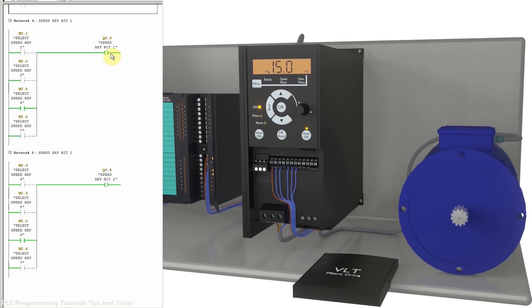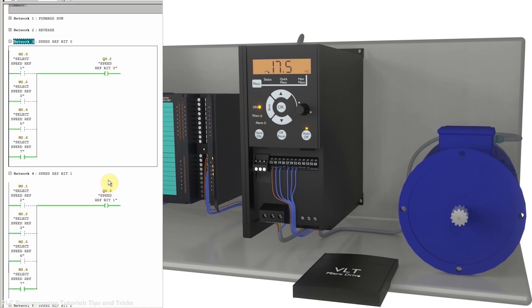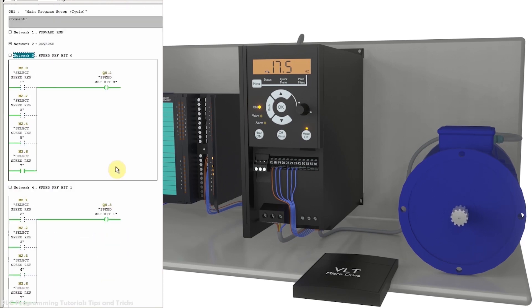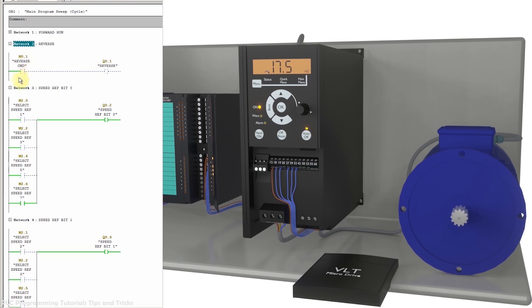Turning on M2.5 loads the sixth preset frequency reference and the motor starts running at 15 Hz. Turning on M2.6 turns on all three bits — their sum is 7 — loading preset reference 7, and the motor runs at 17.5 Hz. To run the motor in reverse, we turn on PLC output Q0.1, which sends a digital signal to the VFD to run in reverse, and the motor starts running anti-clockwise at 17.5 Hz.